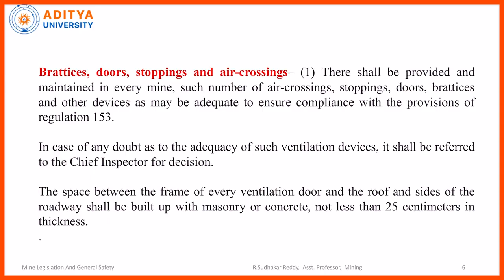In case of any doubt as to adequacy of such ventilation devices, it shall be referred to the chief inspector. If in any mine the manager or ventilation officer is not able to take a decision, then it can be referred to the CIM, Chief Inspector of Mines, who is also called Director General Mine Safety. The space between the frame of every ventilation door and the roof and sides shall be built up with masonry or concrete not less than 25 centimeters in thickness. This space is generally kept to a minimum of 25 centimeters to prevent leakage, which is one of the important things.